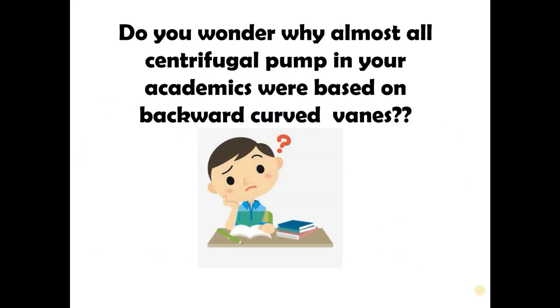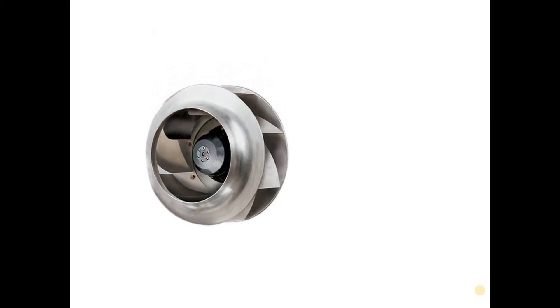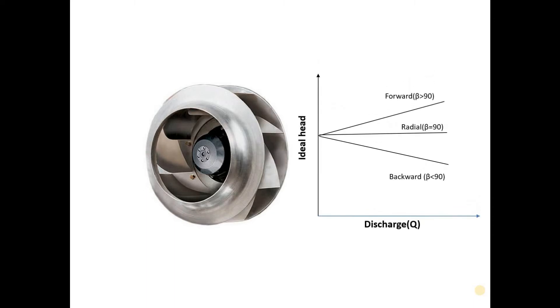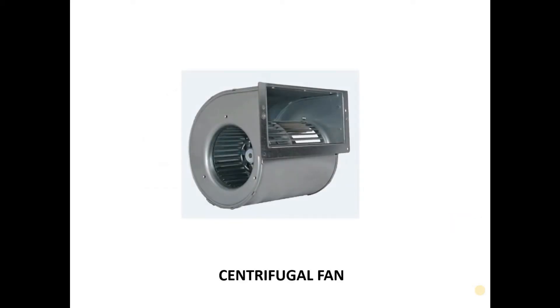Have you ever wondered why all the numericals in your academics were based on backward curved vanes? Backward curved vanes are the most popularly used impellers because there is no stall point on the characteristic curve — meaning there is no point on the curve at which the pump cannot be operated. Forward vanes are used when the fluid concerned is air, as in centrifugal fans.